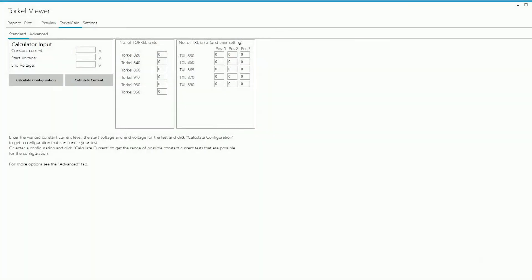The Torkel Calc program is designed to help you do two things. A. If you're planning to run the discharge test at a particular current and you want to find out what configuration would be needed to run the test. Or B. If you have a configuration in mind and you want to find out the current capability of that configuration.